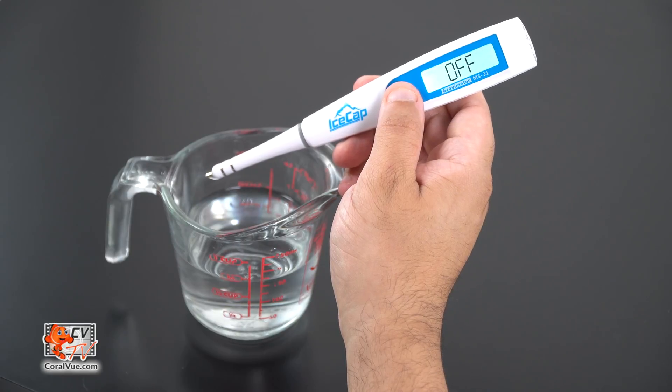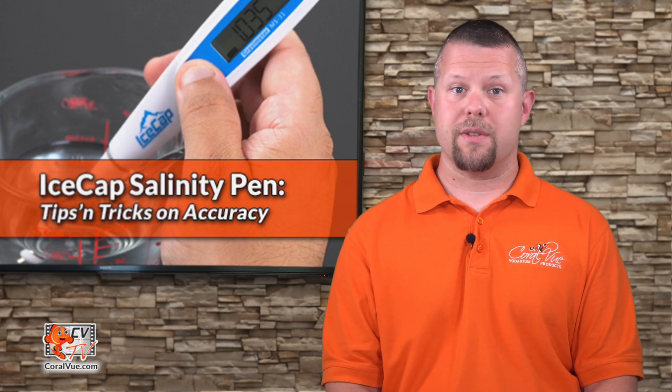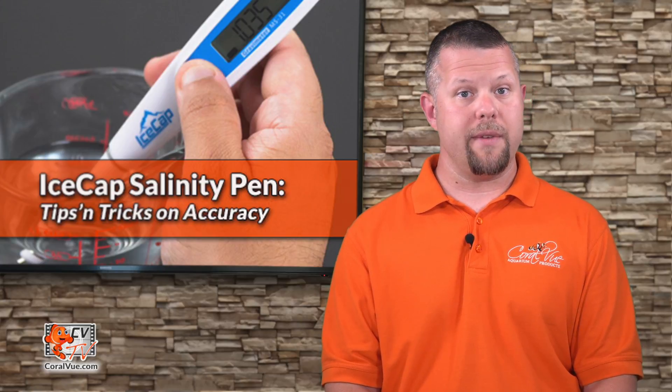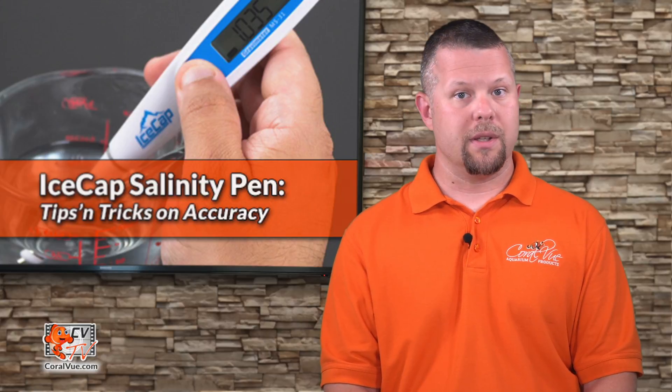Turn the pen completely off to finish the calibration process. Check the accuracy against the calibration solution. To ensure long life and lasting accuracy, rinse, wipe, and store the pen in the included case.